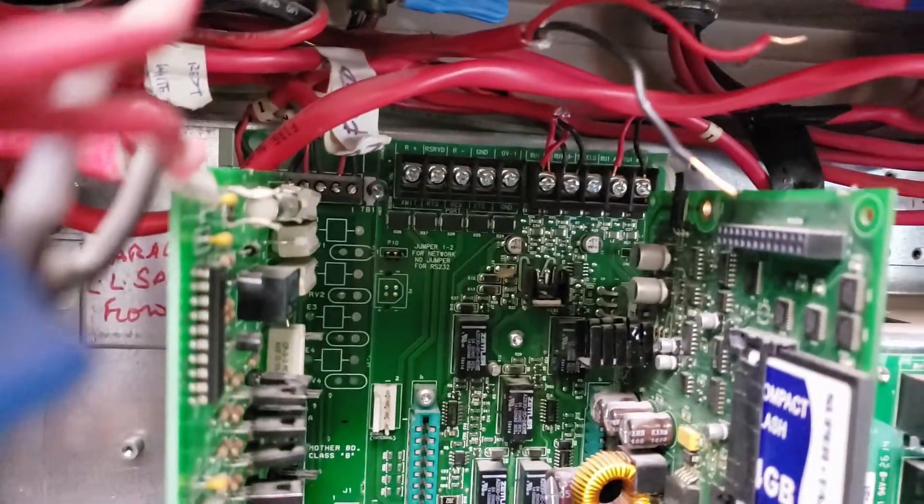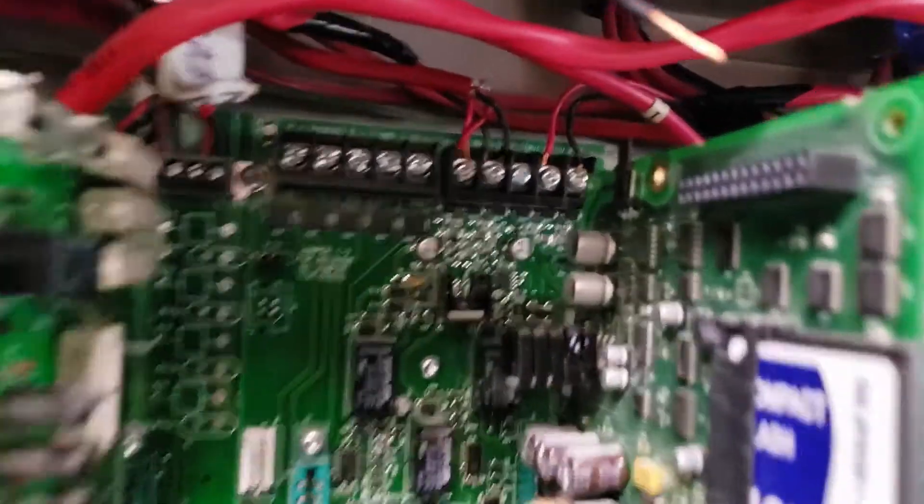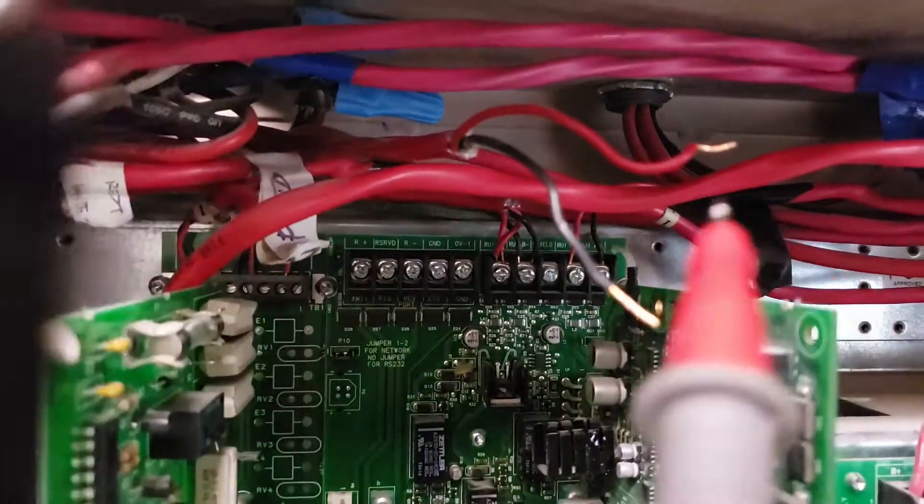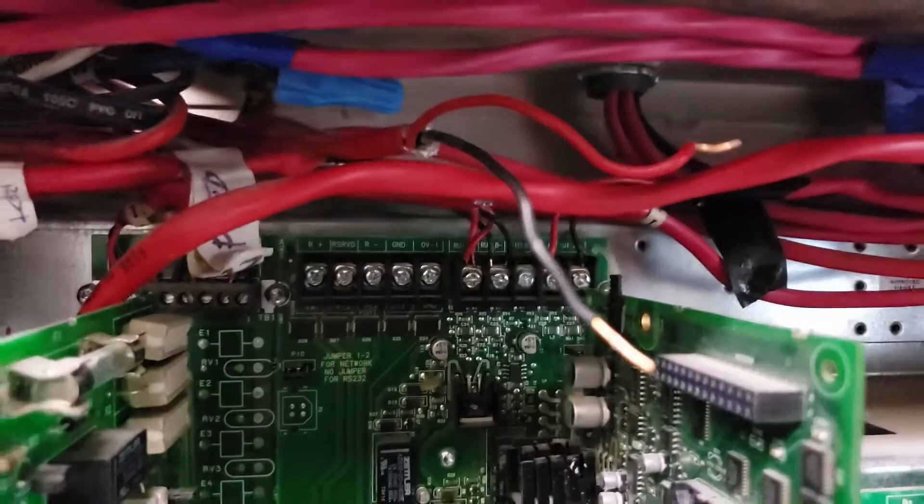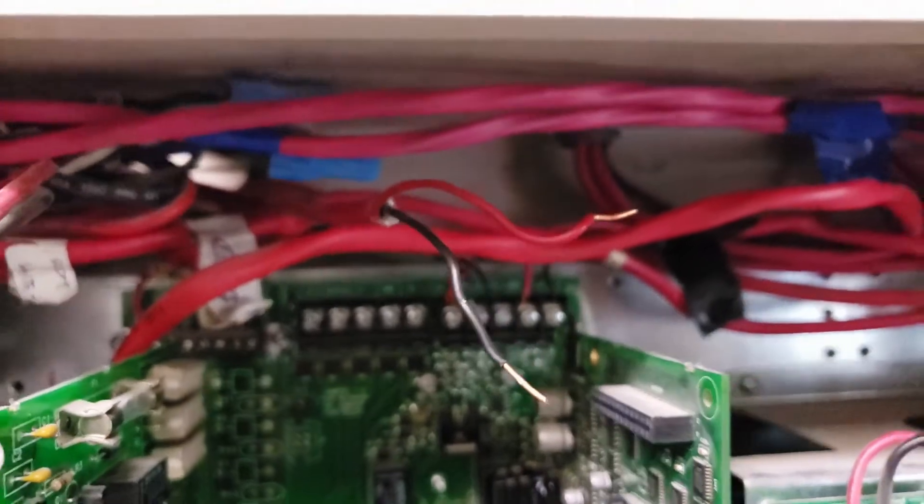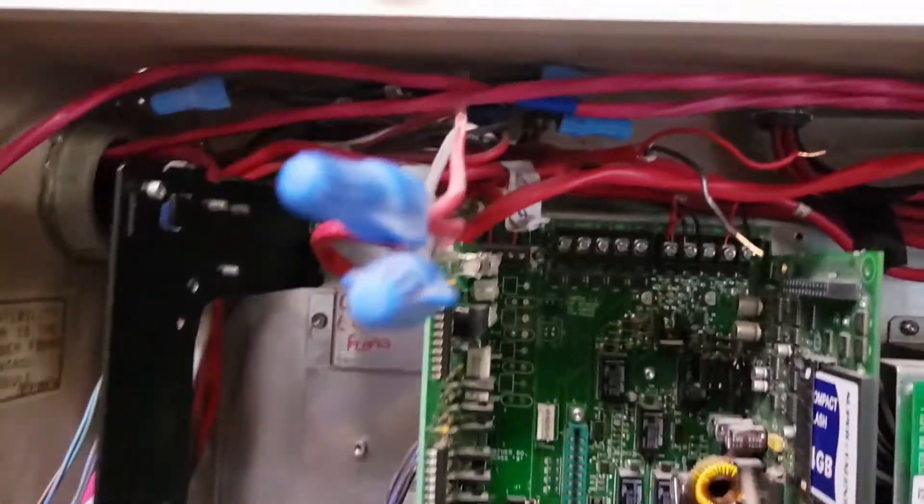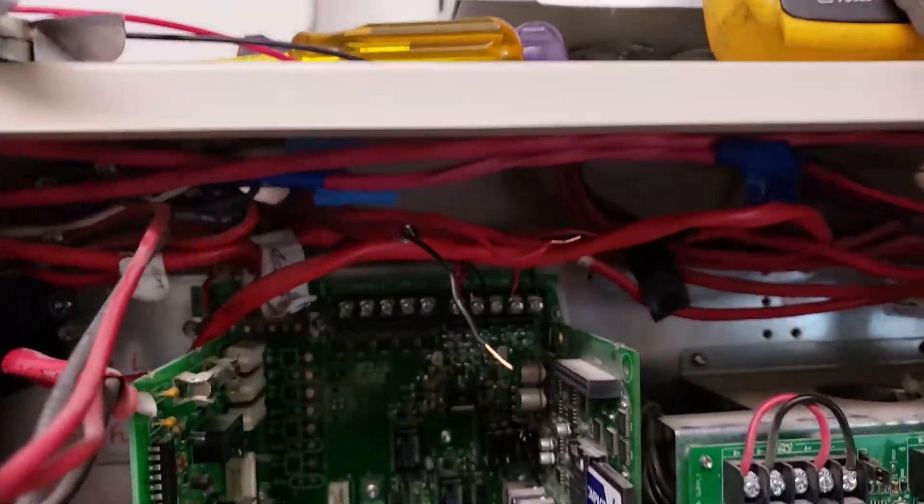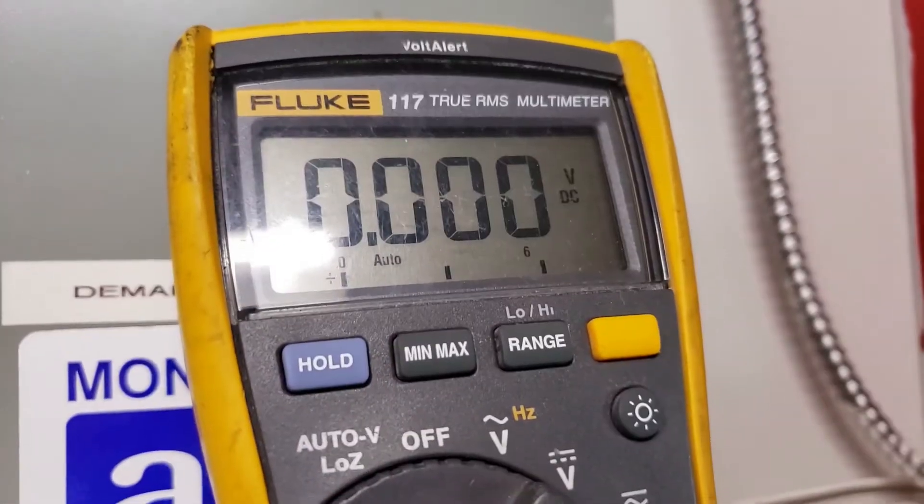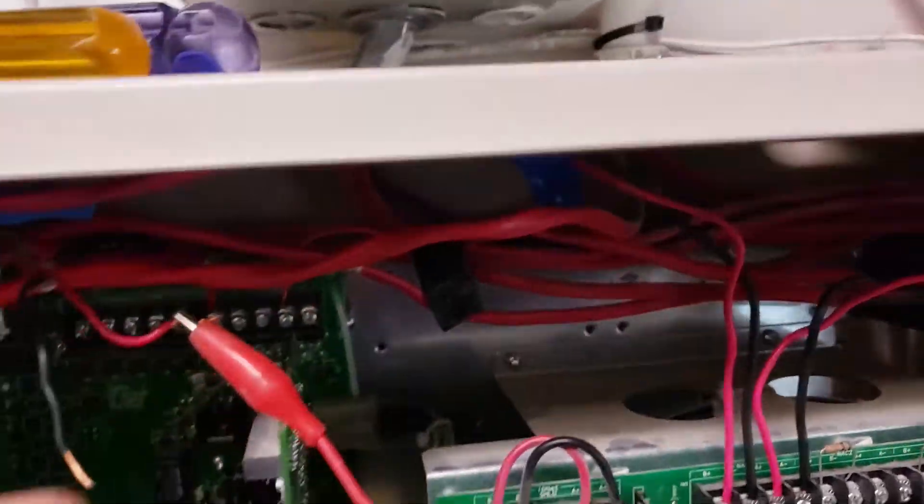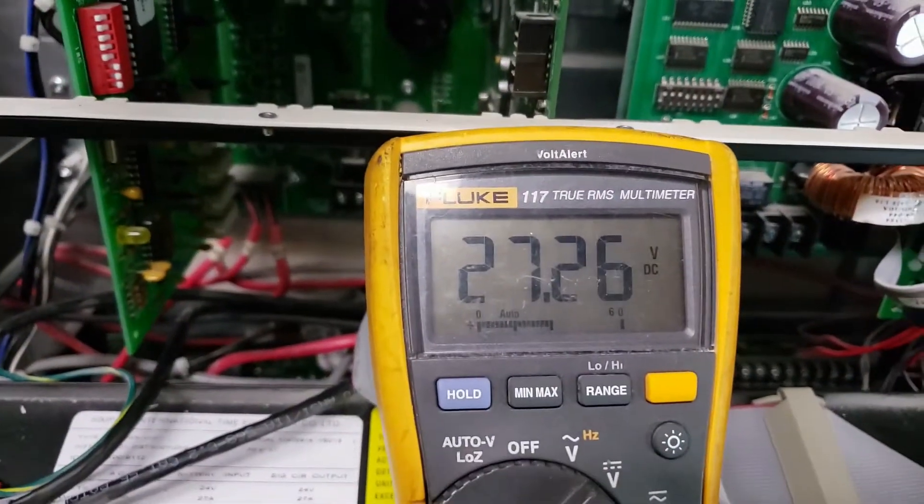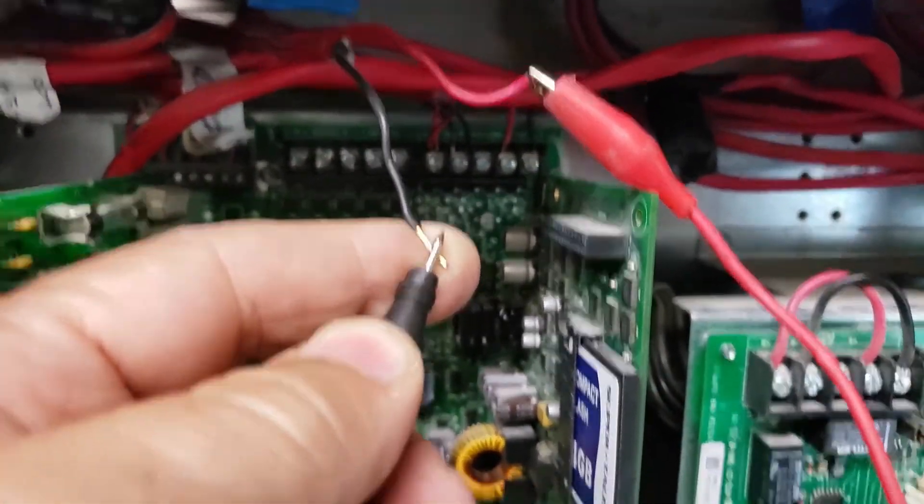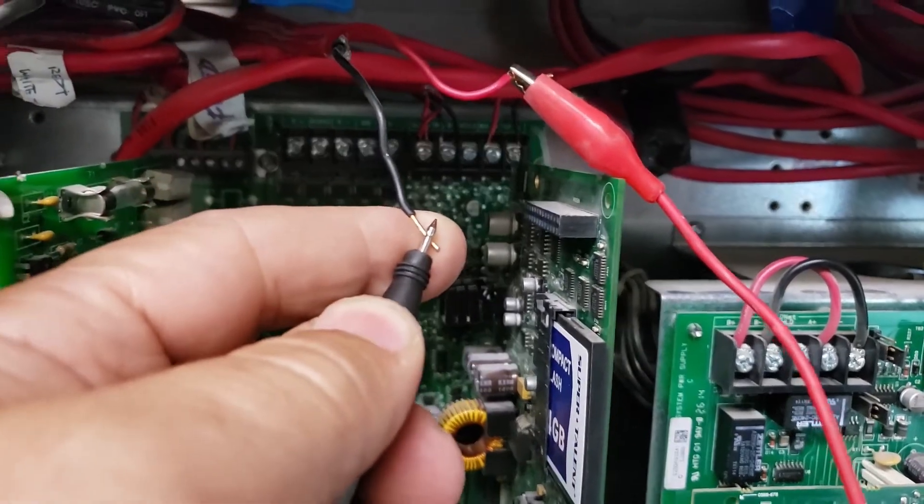Alright, so I think that is what has happened. I've hooked up card 29, piggybacked it on top of the rest of the cards and I've metered this and sure enough, that's the class A side of card 29. This is where I believe our intermittence is coming from. That's the other side of the card 29. They've got a class A on top of a class A and that for sure will cause that intermittent trouble. You can't do that.